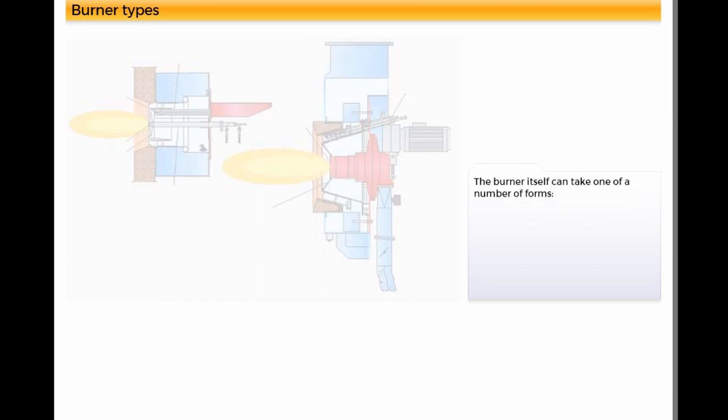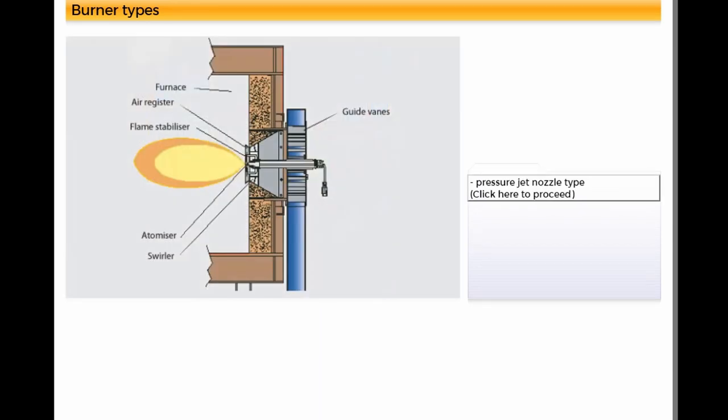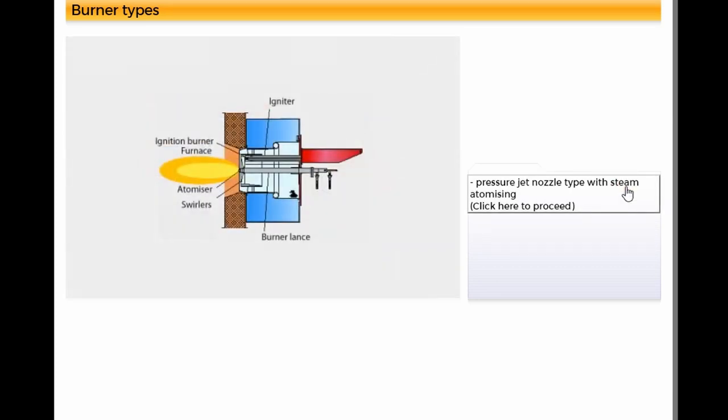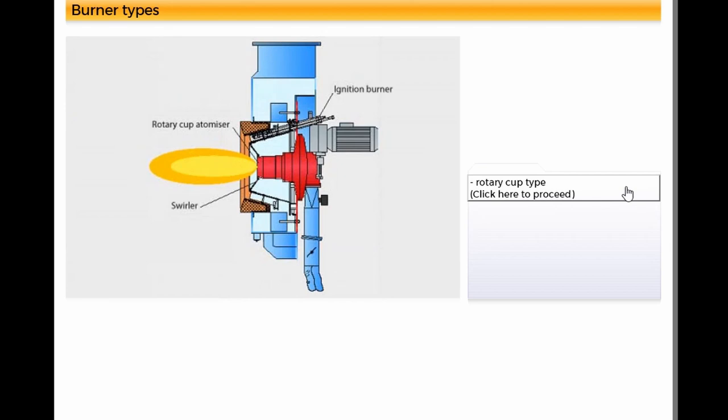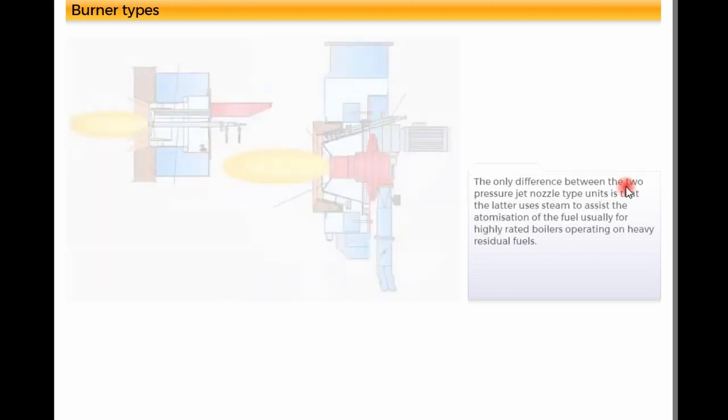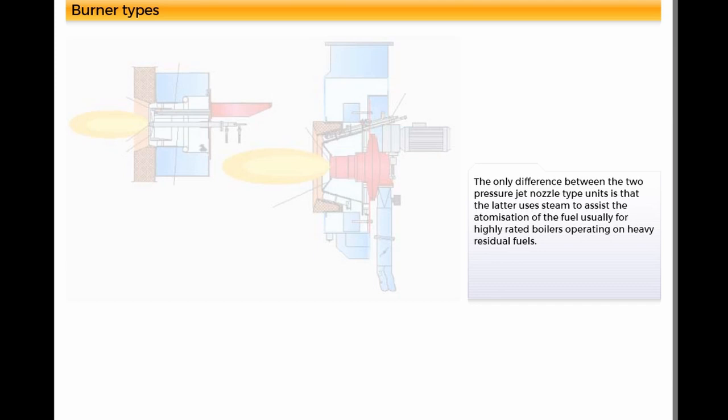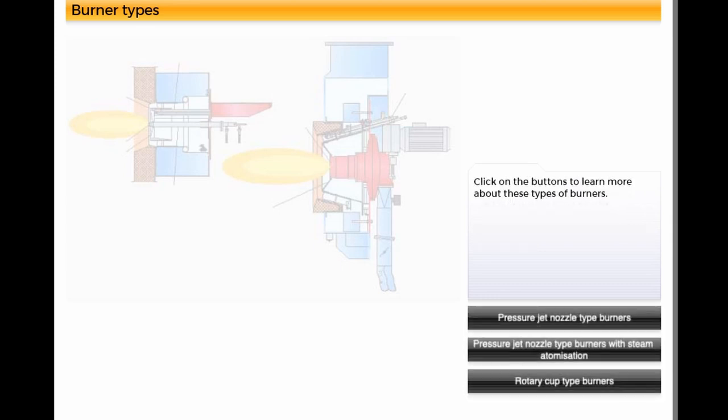The burner itself can take one of a number of forms: Pressure jet nozzle type, Pressure jet nozzle type with steam atomizing, and Rotary cup type. The only difference between the two pressure jet nozzle type units is that the latter uses steam to assist the atomization of the fuel, usually for highly rated boilers operating on heavy residual fuels. Click on the buttons to learn more about these types of burners.